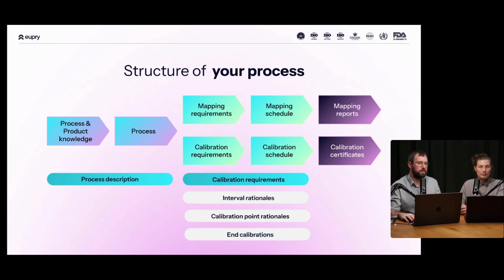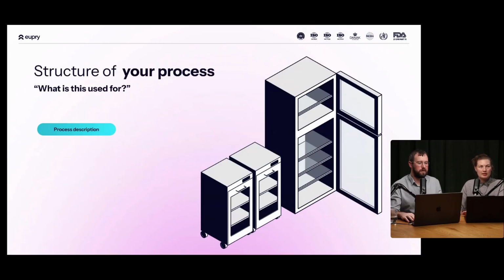We have the calibration point rationales that we've covered, and then the end calibrations, as we just discussed. If you want to know exactly how much your sensor drifted within the time of use, whether it's 1 or 2 years, this is what you can do. You can make an end-calibration requirement, or you can make a risk assessment saying it's not necessary to know this, and look at the product we purchased or rented, and what the requirements are, what the expected drift and accuracy of drift are. In the end, each equipment would have a calibration certificate for each sensor. So this is how you look at your process.